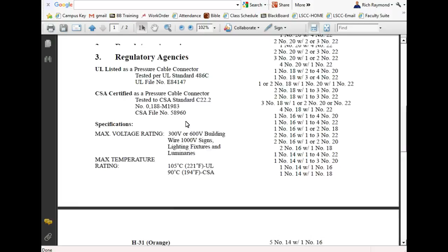Let me find it again — we're going to be using yellow. So we could put 4 to 5 number 22s, 3 to 5 number 20s, 2 to 7 number 18s, 2 to 4 number 16s, 2 to 3 number 14s, or 2 number 12s. You'll see this one used a lot in residential wiring. The two primary wire sizes we use are number 14 and number 12.